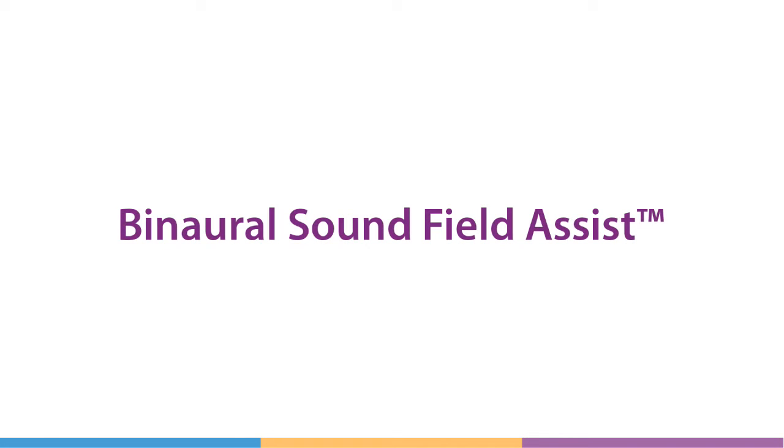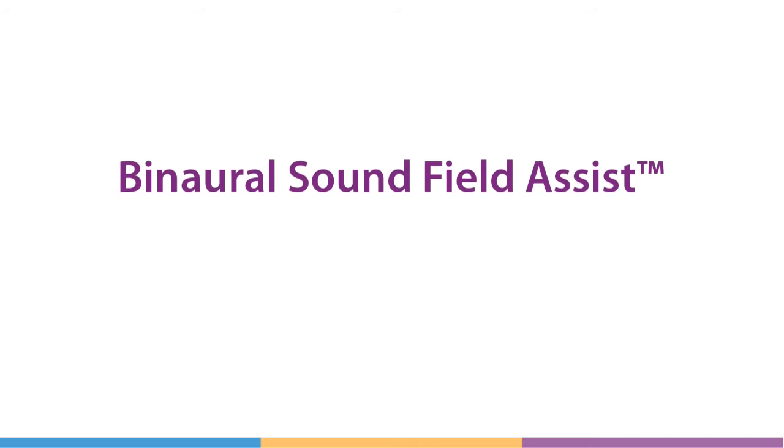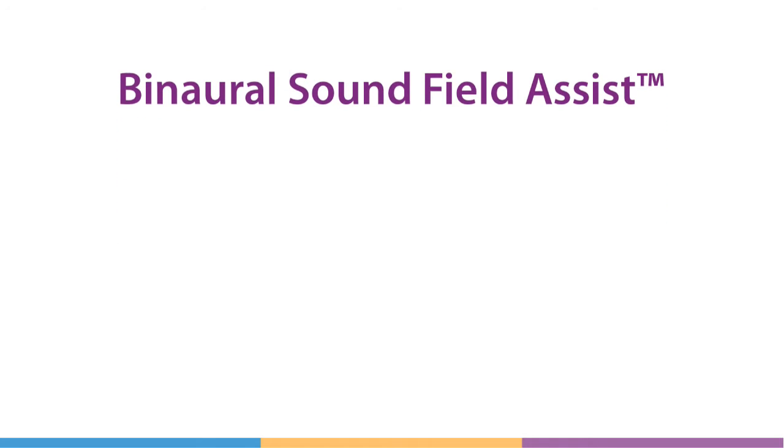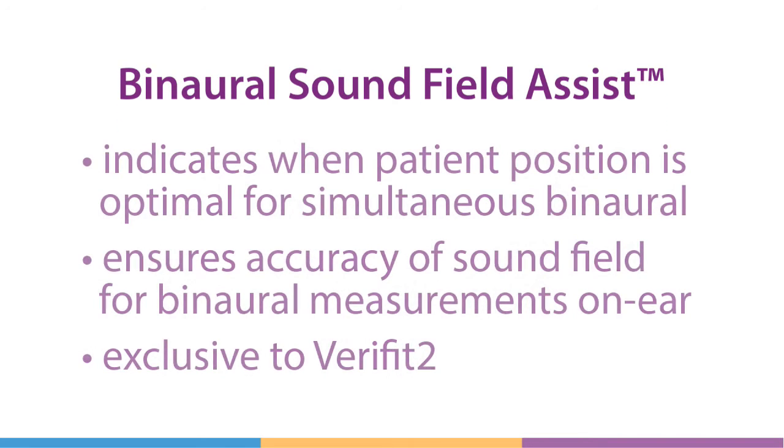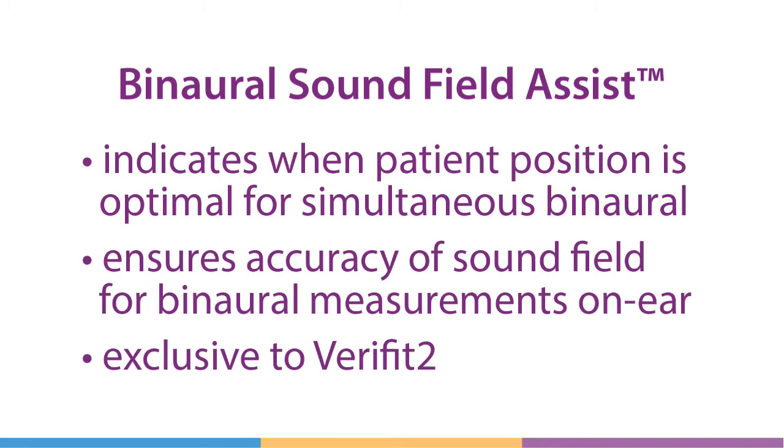To address this issue and guarantee that simultaneous binaural measurements are equivalent to those taken in sequence, the Verifit2 introduces binaural sound field assist. This real-time tool evaluates the sound field at each ear prior to each measurement.